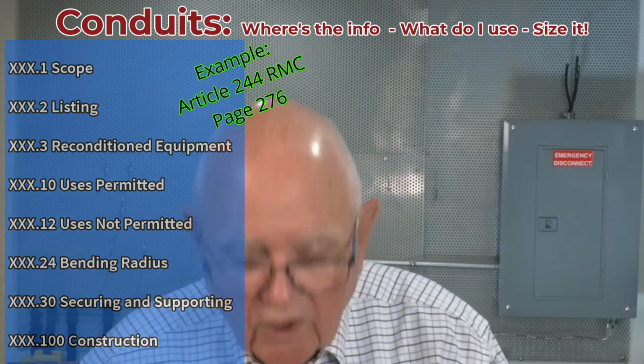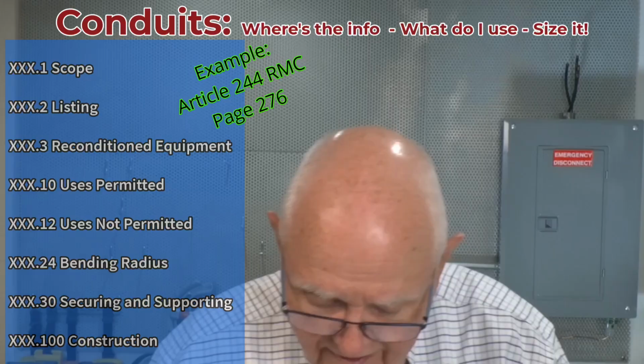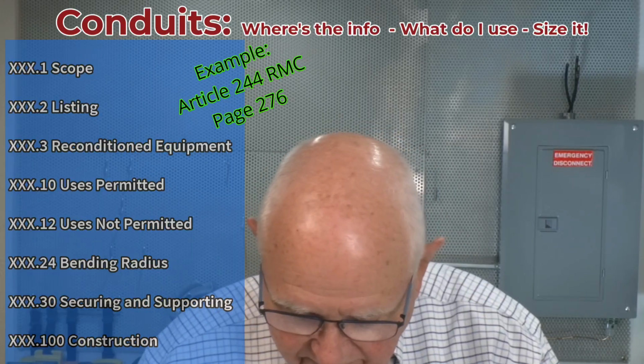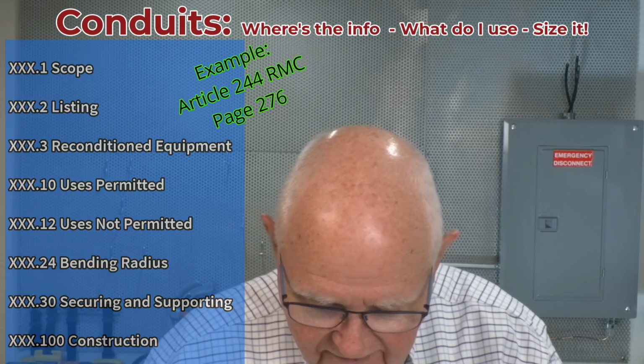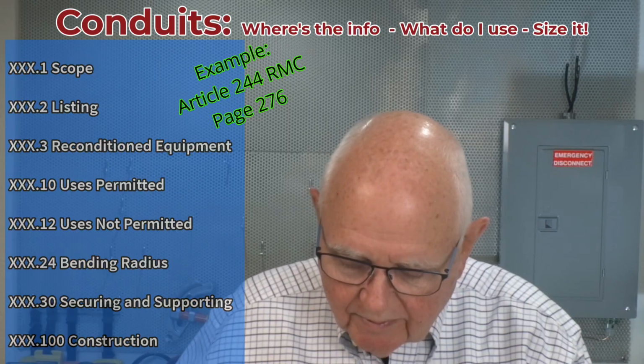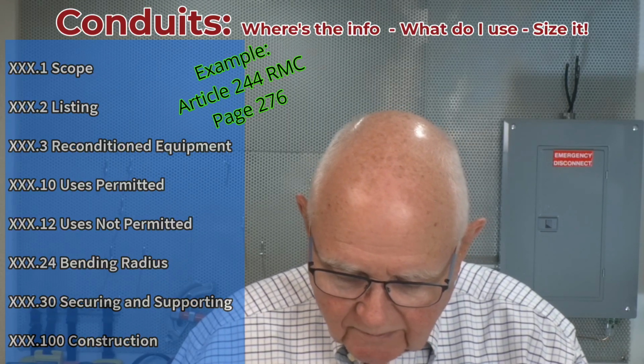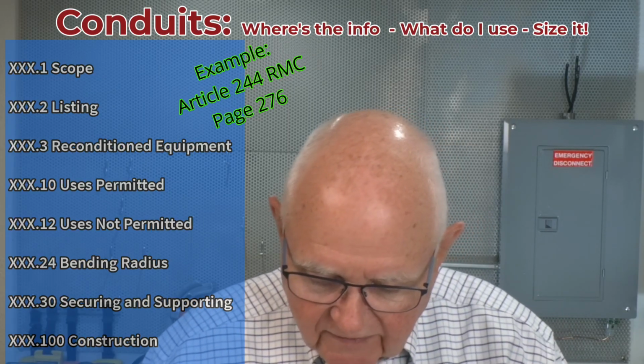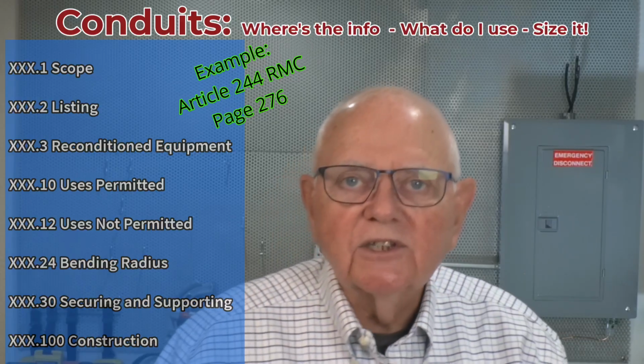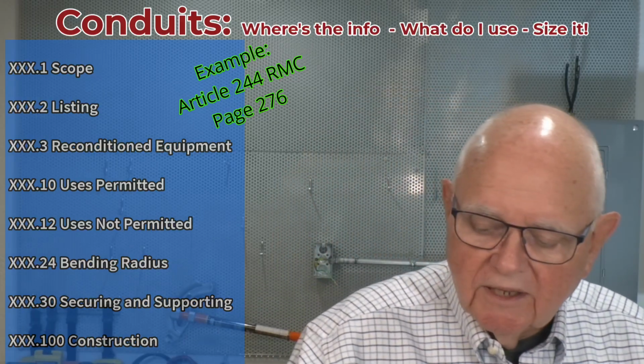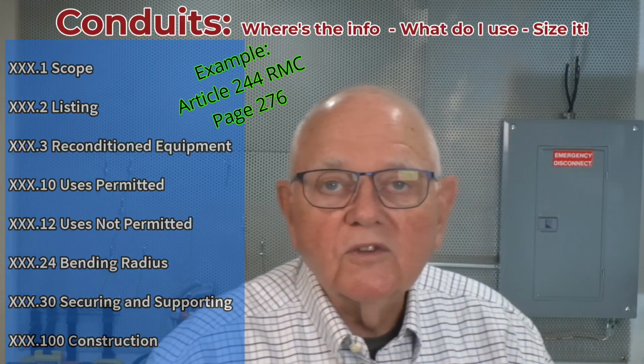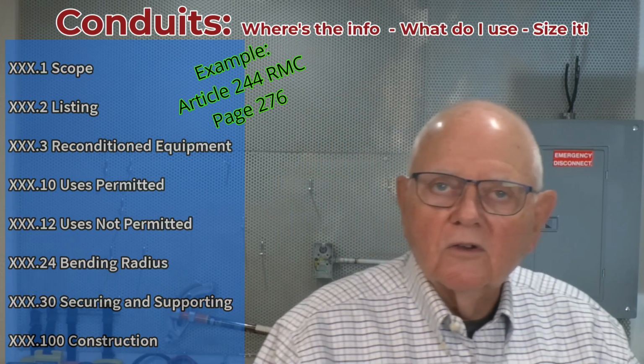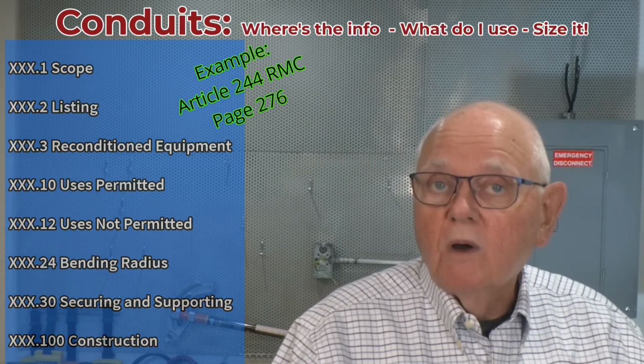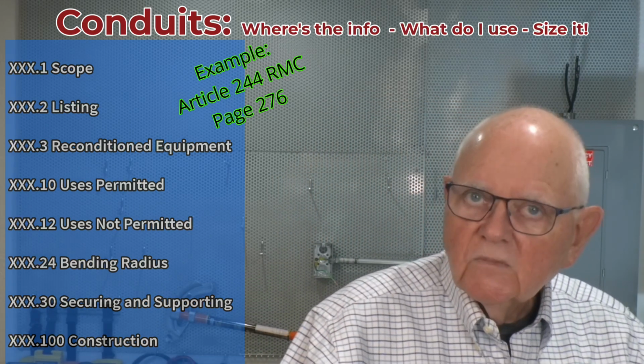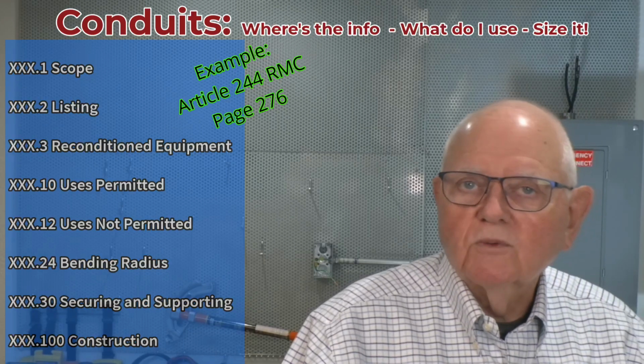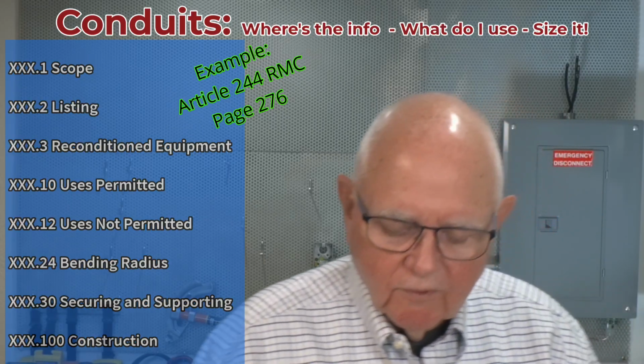Bushings, 344.46. Where a conduit system enters a box, fitting, or other enclosure, a bushing shall be provided to protect the wires from abrasion, unless the box, fitting, or enclosure is designed to provide such protection. That's obviously the big issue. And we have other code requirements. We'll see requirements in that Article 300 on general wiring methods for conductors and raceways, specific requirements for bushings.